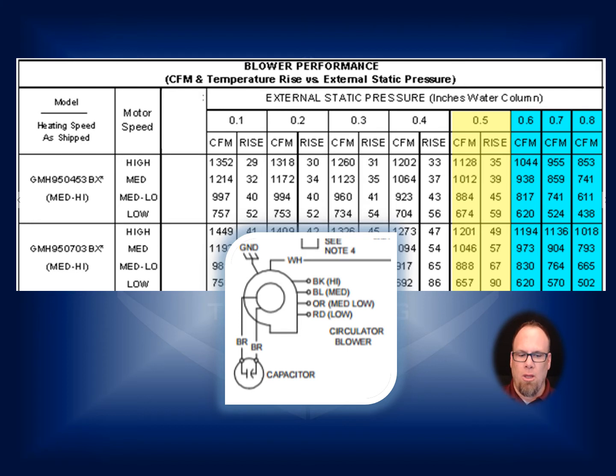Okay, so older furnaces had a temperature rise of around 100 degrees. Newer furnaces of the same BTU value are supposed to be set up around 50 degrees. So what changed? We went from 100 degrees temp rise on the old one to 50-degree temp rise on the new ones. A ton more airflow. That's what we've got to move, is a ton more airflow. So the older ductwork that's in the homes oftentimes is not sized correctly for the modern equipment. It was sized to move less airflow. So we're already starting off with our hands tied on the ductwork, because usually it's all in finished ceilings and walls and floors and things like that. So we have to do what we can to make the airflow right in the home.